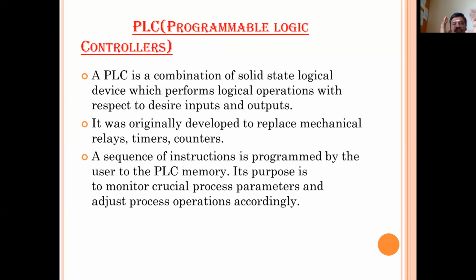So what is a PLC? Programmable Logic Controller. Okay, the PLC is a solid state logical device. It performs logic operations with respect to the input and output. It replaced relays, and moreover the mechanical relays, timers and counters were replaced by soft instructions, just a program.